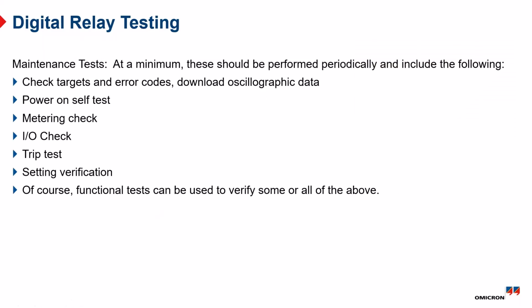Maintenance test on a digital relay. So this is after it's installed, periodically. Right now, PRC-005 on an unmonitored device on the bulk electric system has to be retested every 6 years. So that's the standard, and they don't care if somebody was on vacation or you had an outage or whatever, that you didn't get to something on time. I think the fine last I heard was $5,000 per device per day for a device that's out of compliance. So it's serious business.